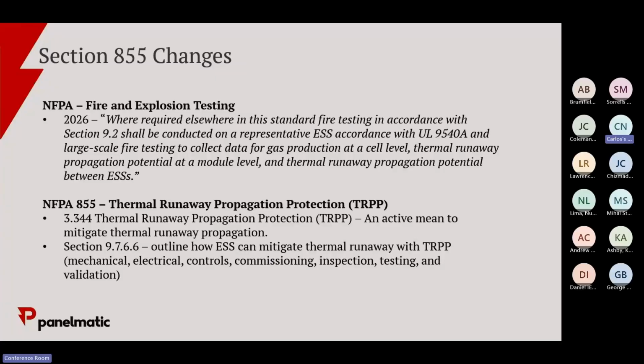Thermal runaway propagation is another one, outlining how thermal runaway events occur and trying to prevent propagation not only cell to cell or module to module, but now also unit to unit. Most of the time these enclosures or systems are sitting stacked very closely beside other ones, so this is about how you can mitigate so that if a thermal runaway event occurs, it doesn't propagate to something beside it.